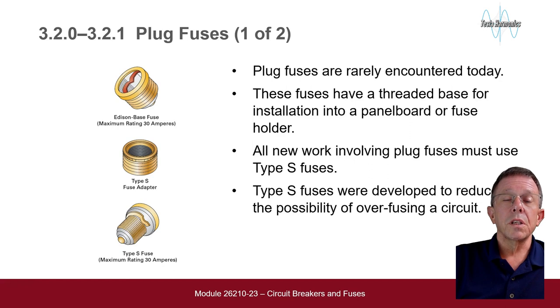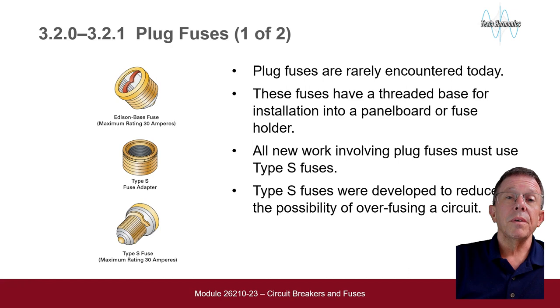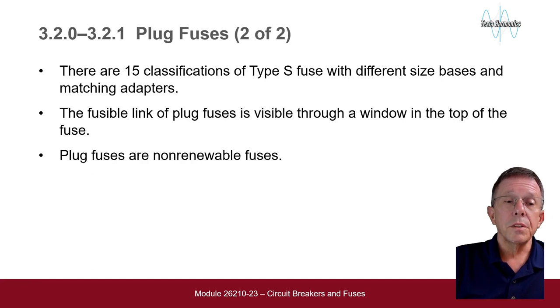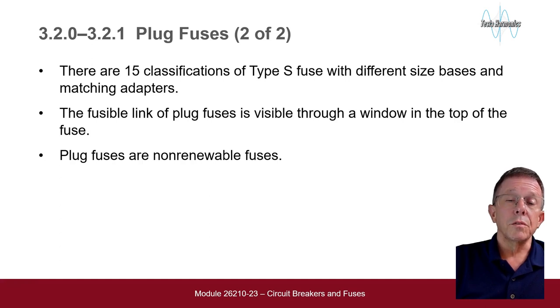Plug fuses are rarely encountered today. These fuses have a threaded base for installation into a panel board or fuse holder. All new work involving plug fuses must use Type S fuses. Type S fuses were developed to reduce the possibility of overfusing a circuit. There are 15 classifications of Type S fuses with different size bases and matching adapters. The fusible link of plug fuses is visible through the window at the top of the fuse. Plug fuses are non-renewable fuses.